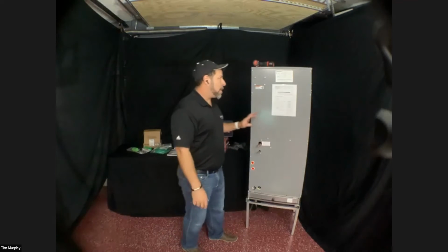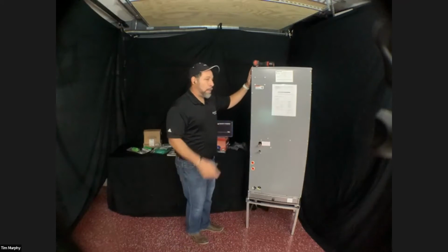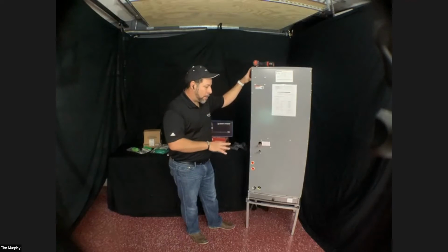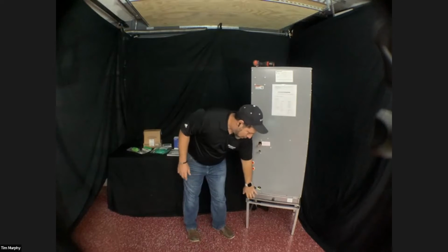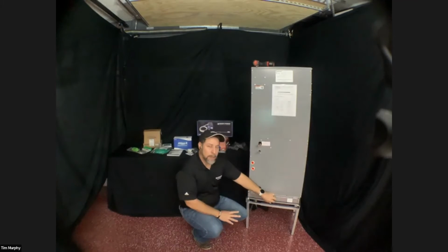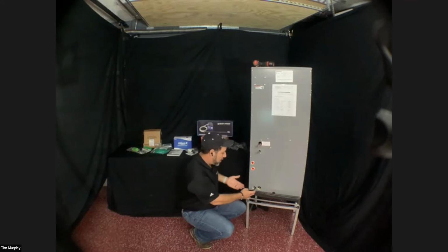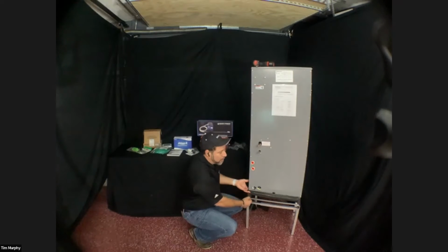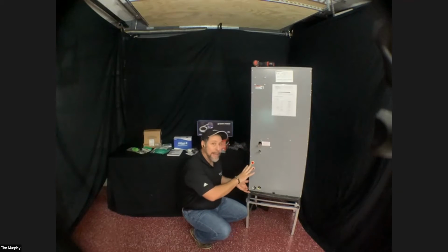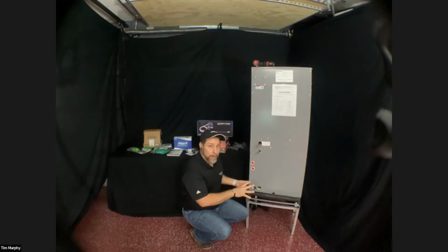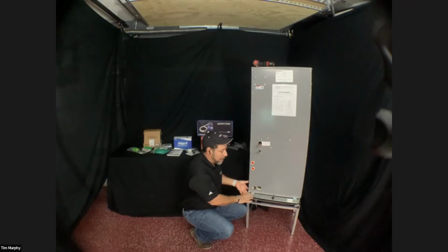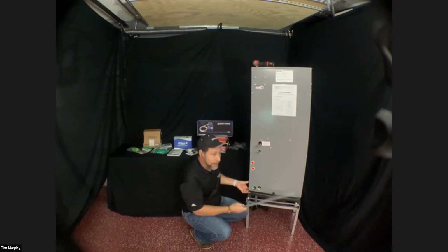Okay, some of the other things that we want to look at here, before I put the head cam on and we start getting deeper into it. If you look down here, this is our Ruud filter rack that we sell for all our Ruud units. So it will fit, as you can see, using this filter rack. And why is that important? Just like anything else, static on an inverter system is very important. So I highly recommend utilizing this filter rack, pulling these rails out. There's rails on each side, if you don't know this already.